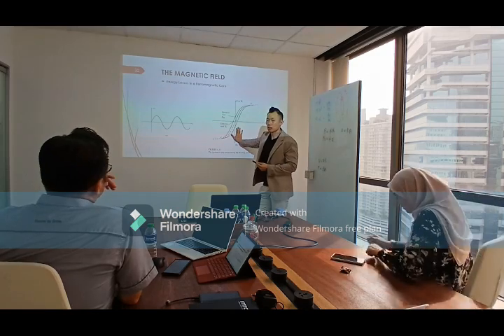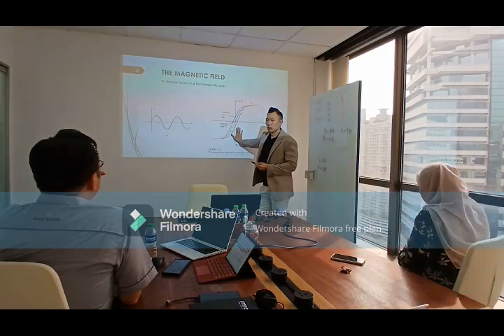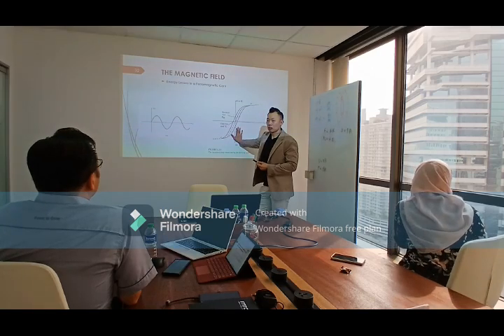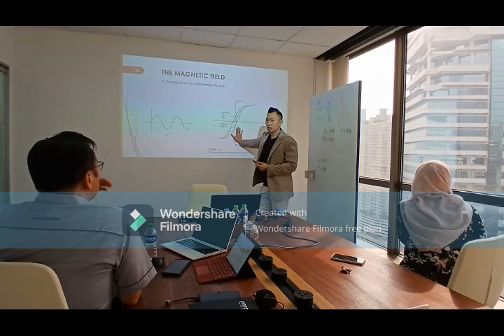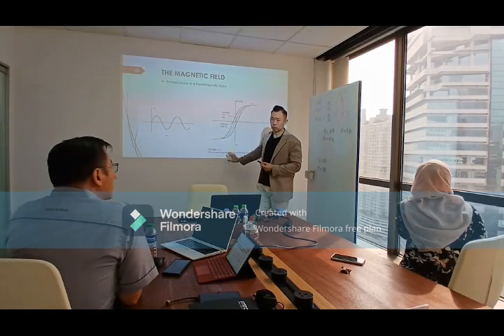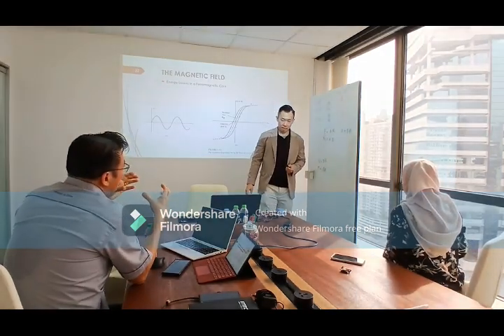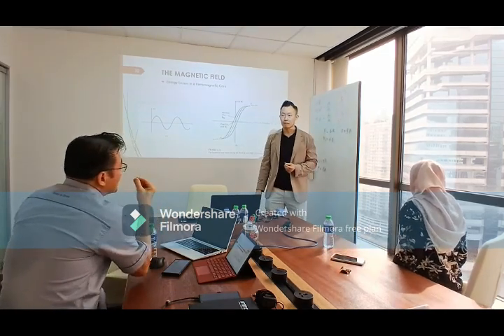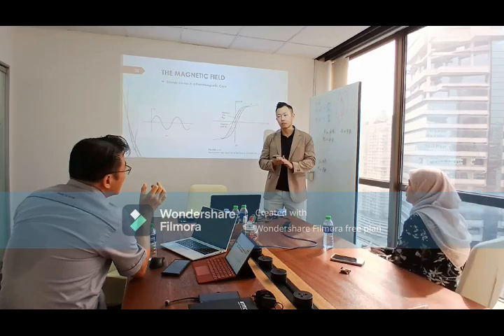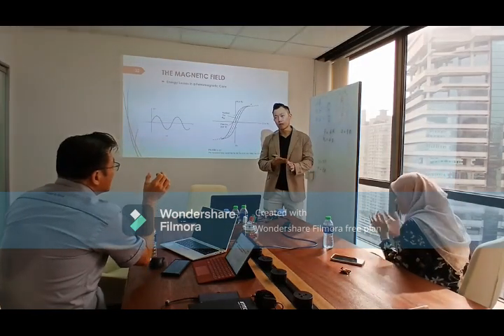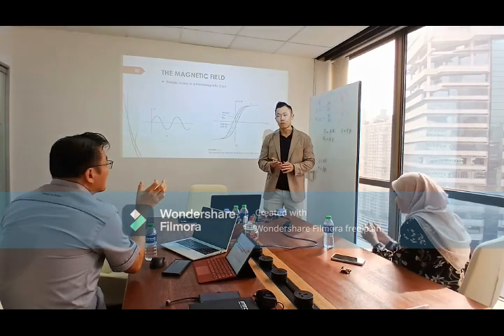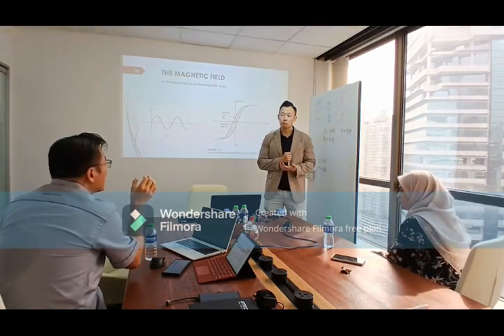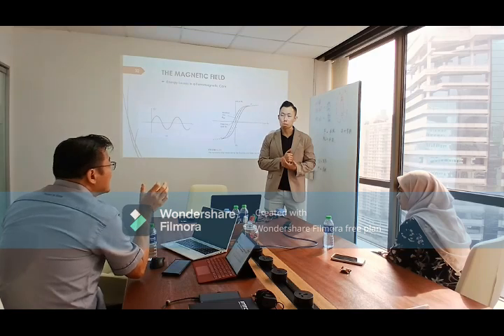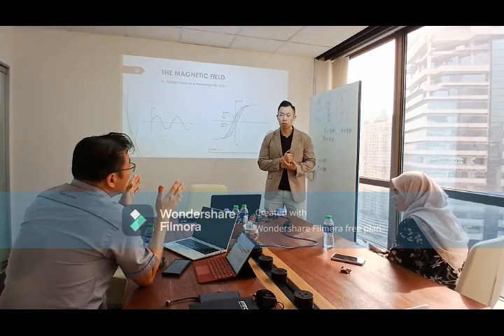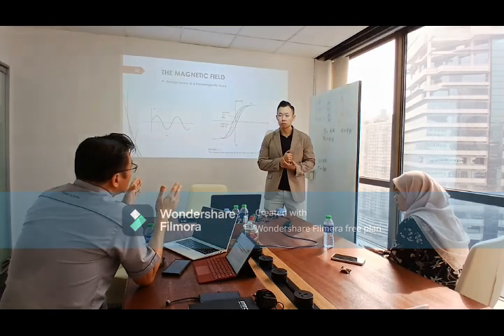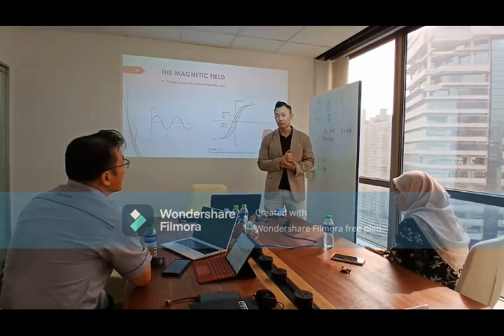I see. Because just now when we talk about the magnetic field, magnetic flux, it only deviates or changes due to the current itself or the voltage. With the voltage, let's say now our motor is rated at 6.3 kV, with a rated current of let's say 20 amps. If the voltage drops, the operating voltage, let's say now it becomes from 6.3 to 6,000 or even lower, 5.7, the current relatively will be higher in order for us to get the operating power for the motor, right? So yes, this will affect the magnetic flux of the motor.